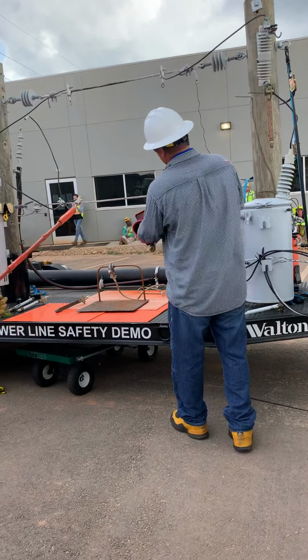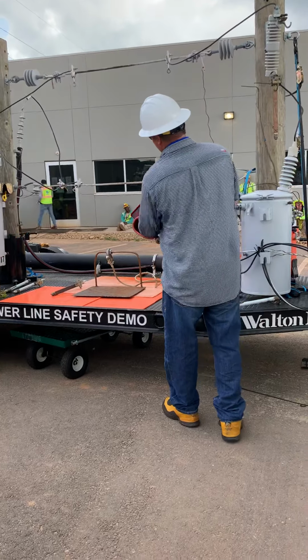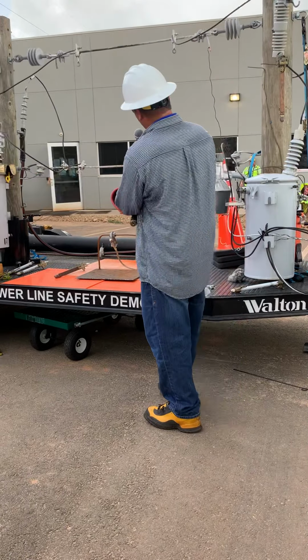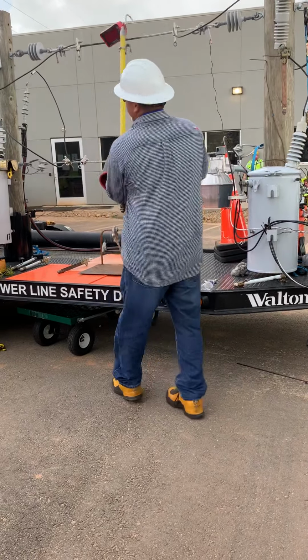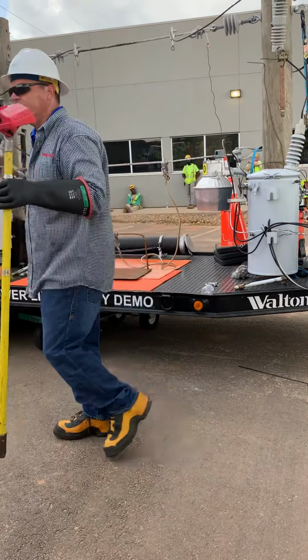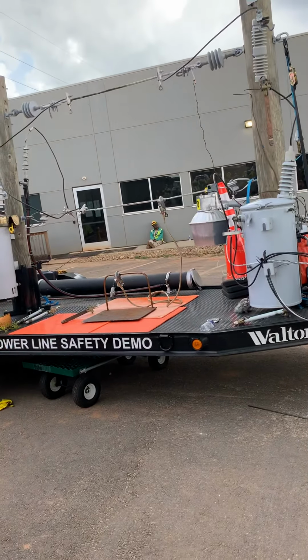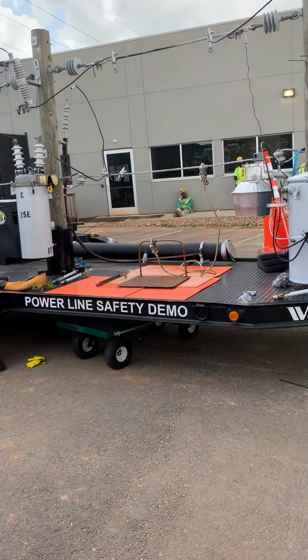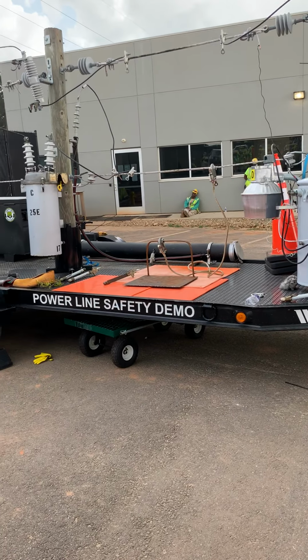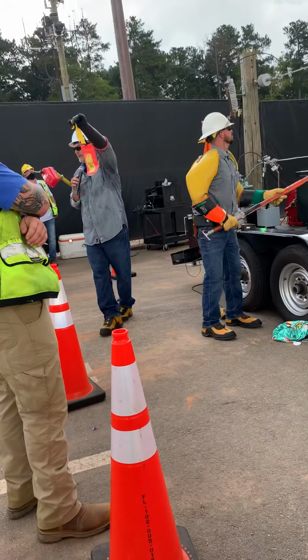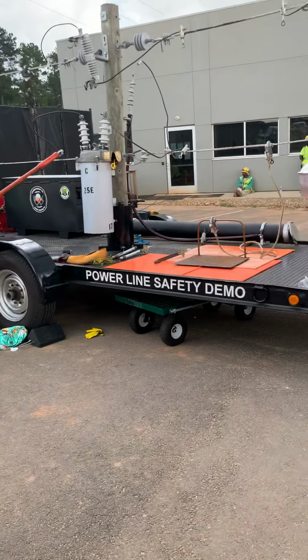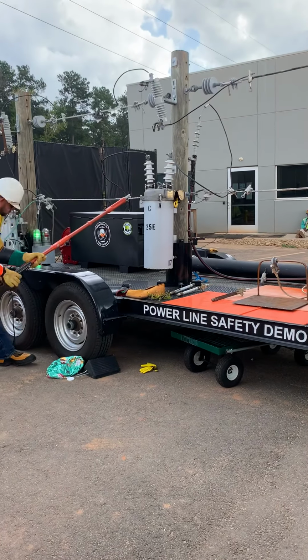We take a ground, this is what we use right here. A 1/0 copper with clamps on it. We clamp it on the neutral, we clamp it on the primary, on both sides of the work area. And then we'll take a tag, just like this one, and we'll hang it on that device. It says hold tag, do not operate. Then we can come out of our gloves and sleeves or any of our PPE.